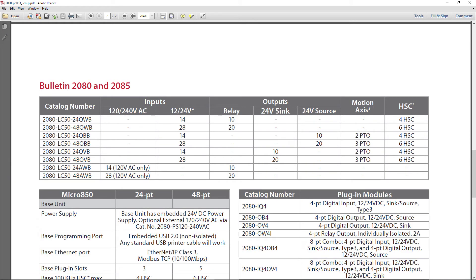So high-speed counter counts all of those counts, and then when it's time to update the input, it doesn't get an on or off, it gets an integer value to say how many pulses it counted between program scans.